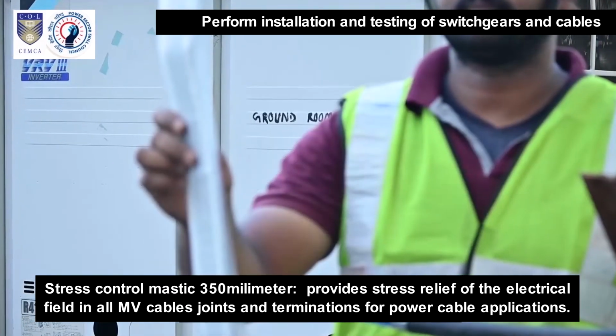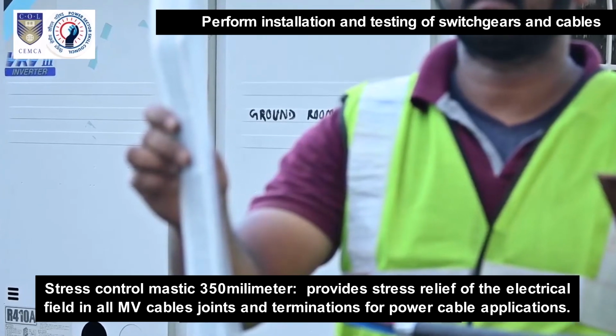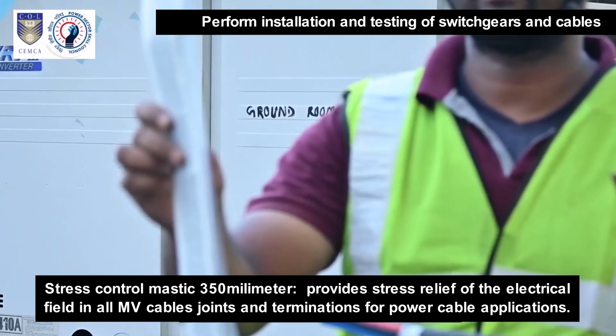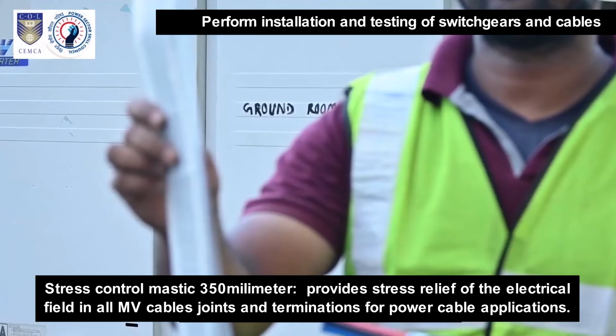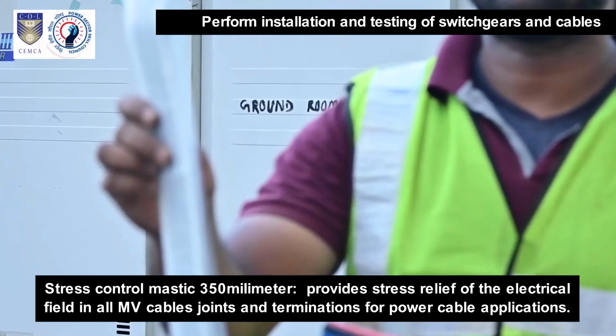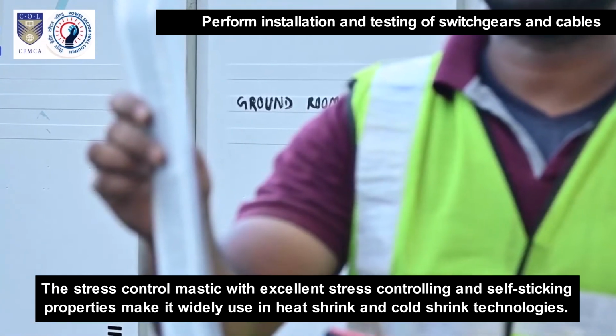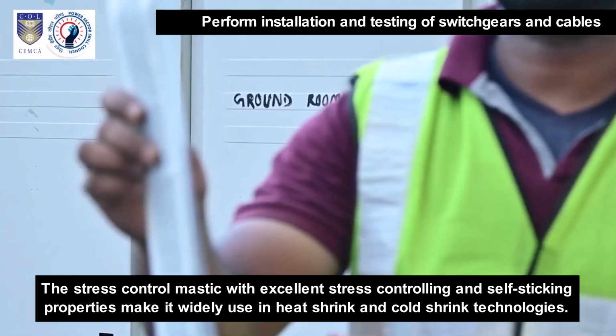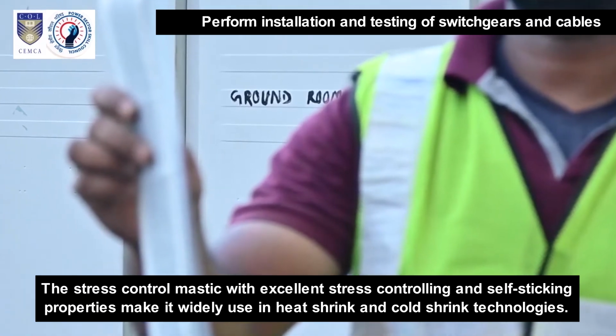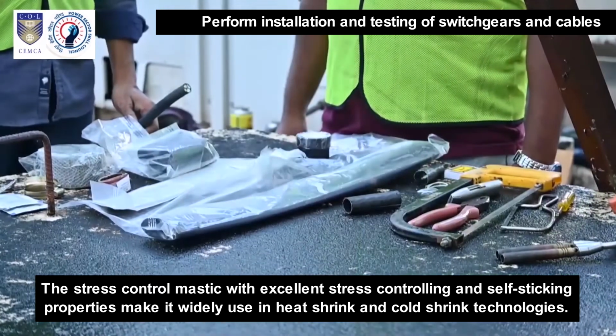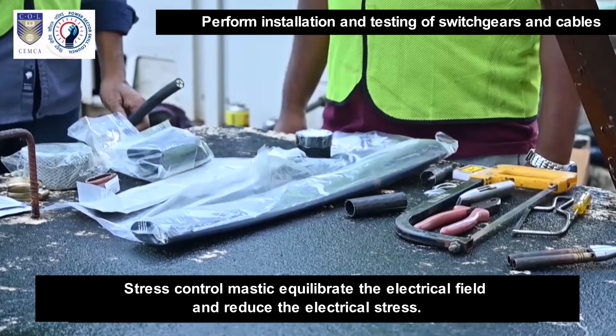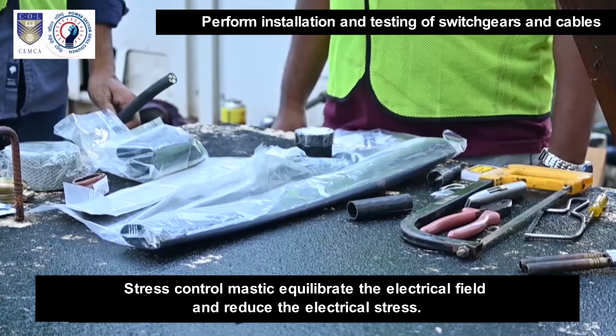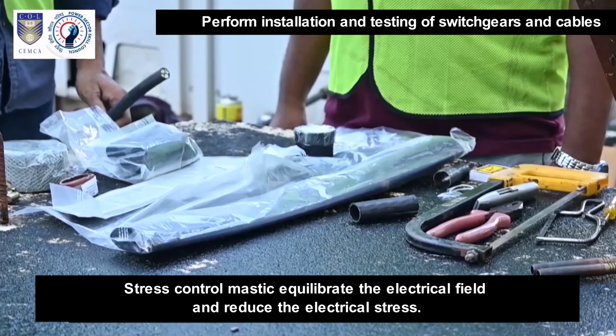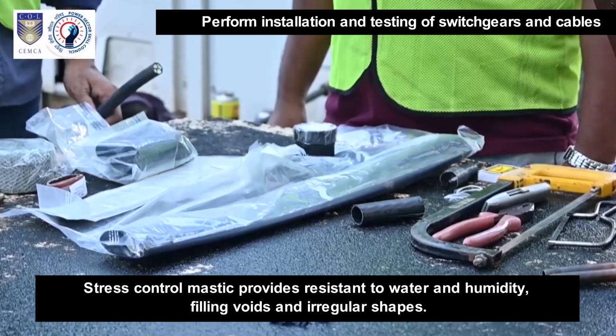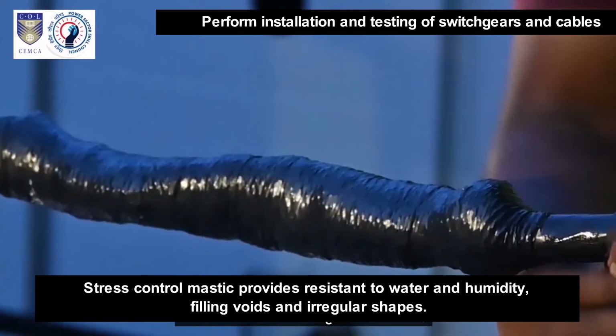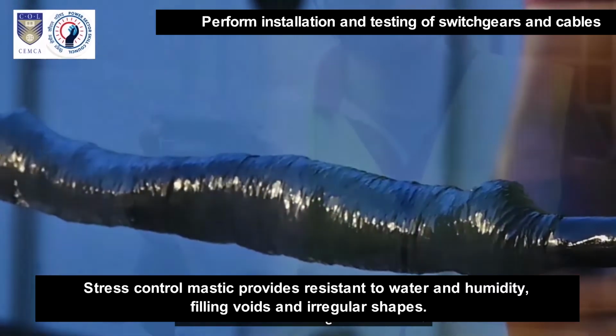Stress control mastic 350 mm provides stress relief of the electrical field in all MV cable joints and terminations for power cable applications. The stress control mastic, with excellent stress controlling and self-sticking properties, makes it widely used in heat shrink and cold shrink technologies. Stress control mastic equilibrates the electrical field and reduces electrical stress. It provides resistance to water and humidity, filling voids and irregular shapes.